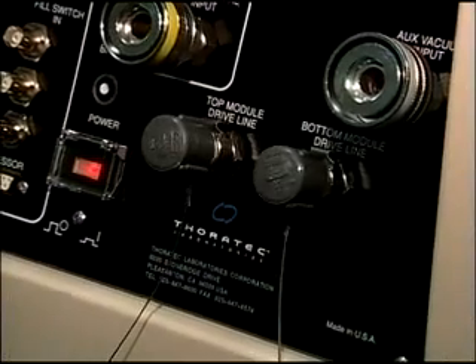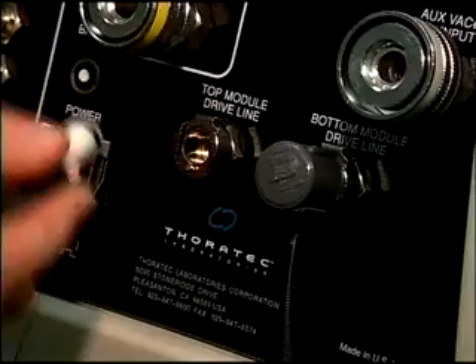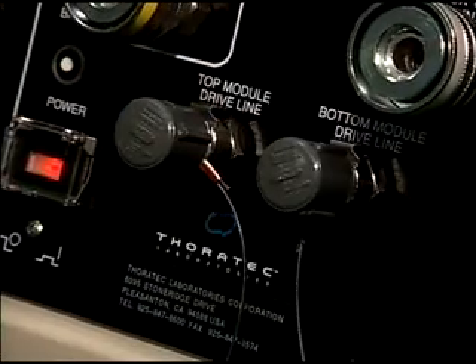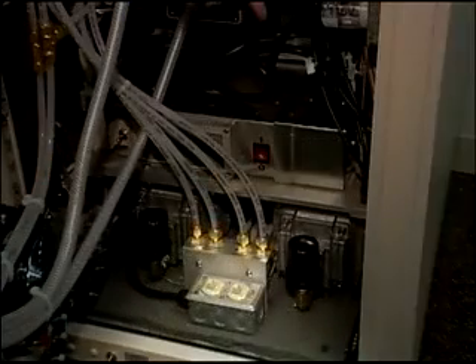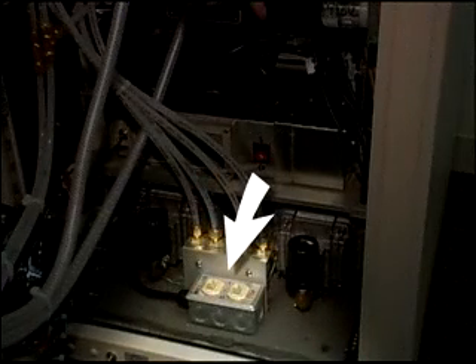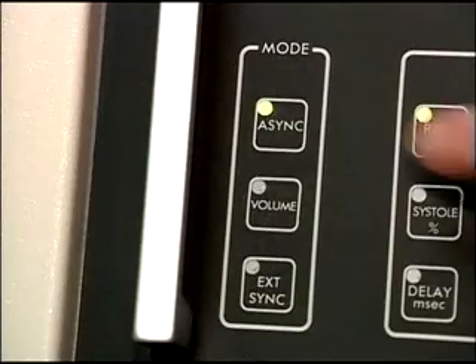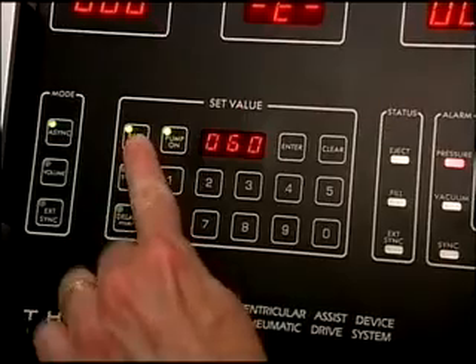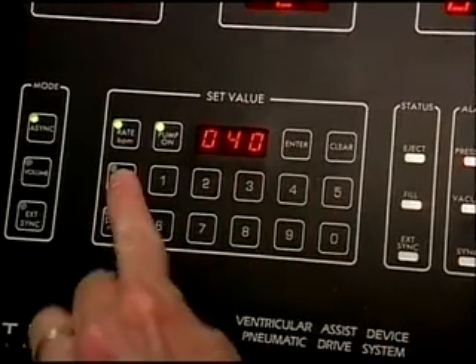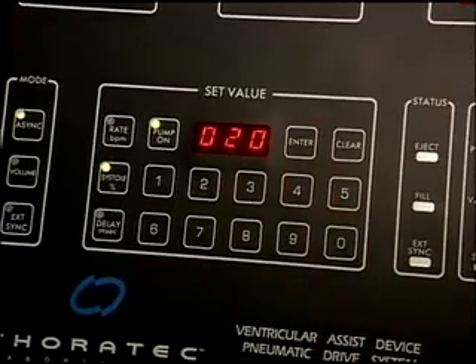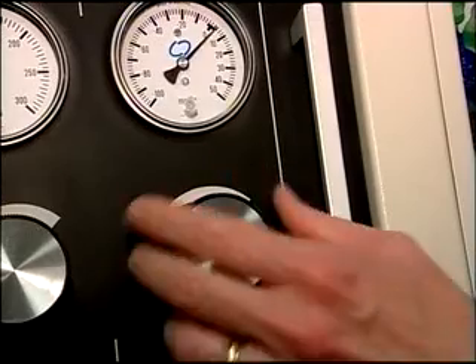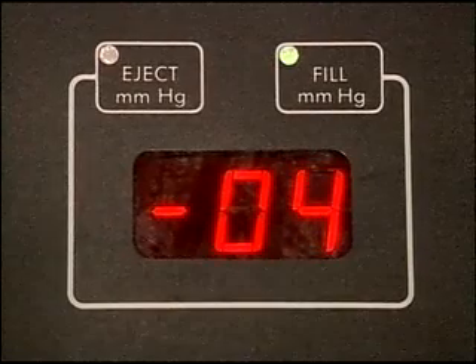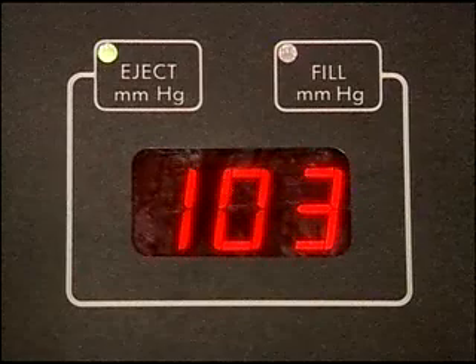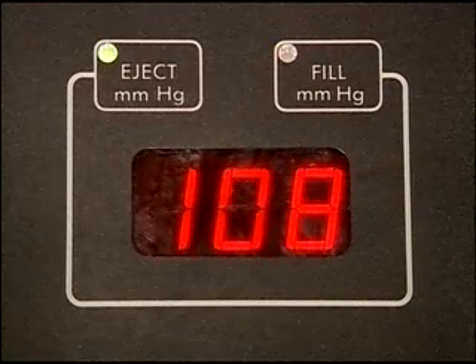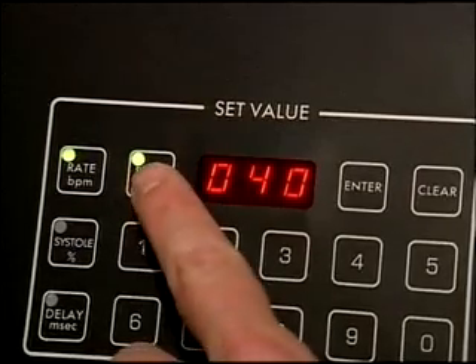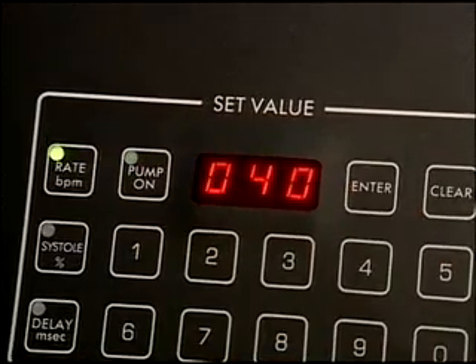While the VADs are being implanted, the console should be prepared for use. Occluders on the pneumatic ports will allow the operator to preset eject and vacuum levels. Turn on the compressor switches for the top and bottom modules. Verify that each drive module is in async mode. Preset the starting rate at 40 beats per minute with a systolic percentage of 20. Set the vacuum between 0 and -4. Finally, set the eject pressure between 100 and 110 millimeters of mercury. The pump can now be turned on by pressing the Pump On button and then the Enter button.